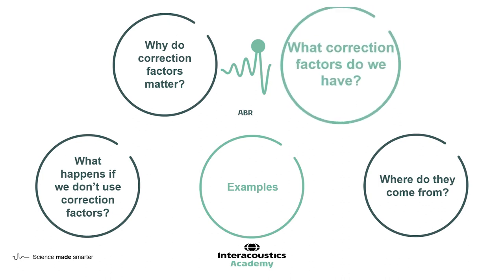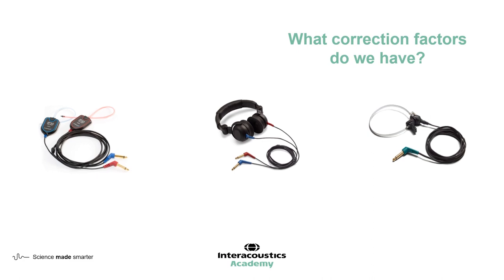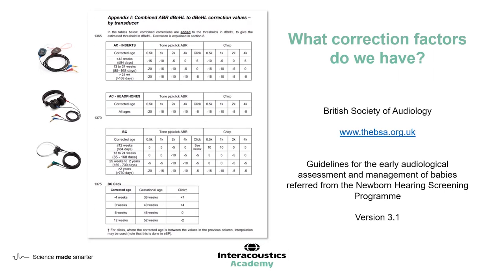So what correction factors do we have available? If we go beyond the evoked potential system itself, a step further down the line, is the transducers that are used to deliver stimuli to our babies. These different transducers each need their own correction factors, because they deliver that stimuli in different ways. Many people refer to the British Society of Audiology guidelines — a freely available document which has comprehensive correction factors available for ABR testing, provided by transducer and in age brackets.